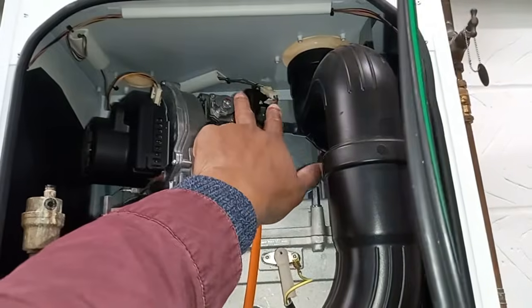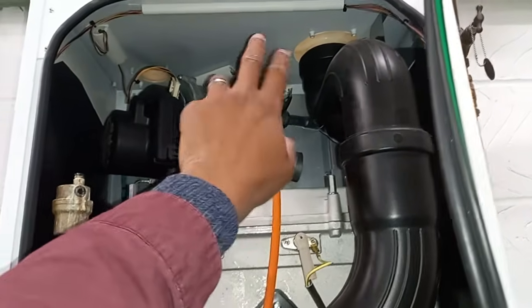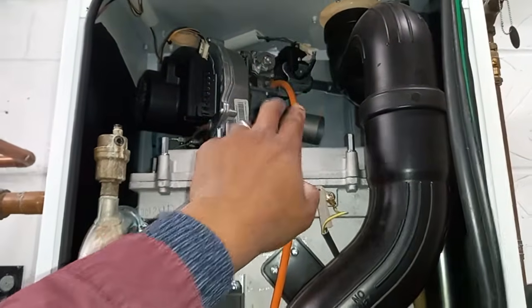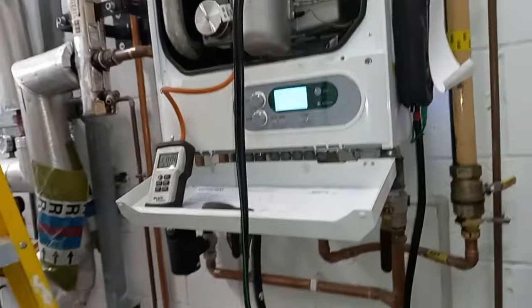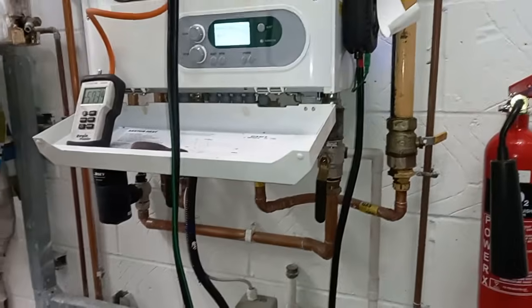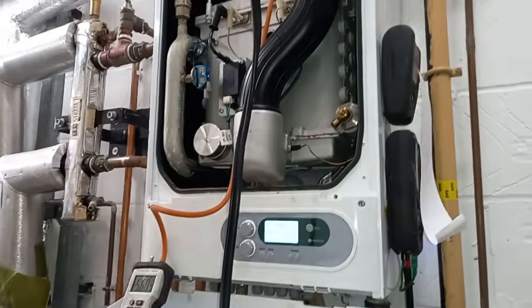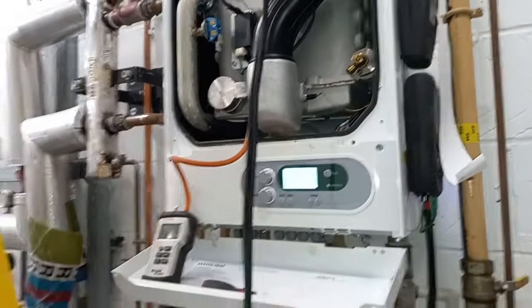Another test you can do is you can check the resistance. I believe on this one it's the 2 outer pins, but you can check the resistance on it and what it should be. So it's doing its attempt to light here, and I should be counting how long it takes for the safety shutdown for it to go into lockout. You can check with the manufacturer the time if it's correct.